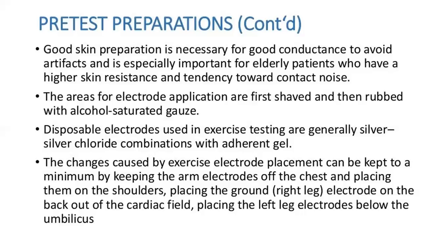The areas of electrode application are first shaved and then rubbed with alcohol saturated gauze. Disposable electrodes used in exercise testing are generally silver chloride combinations with adherent gel.